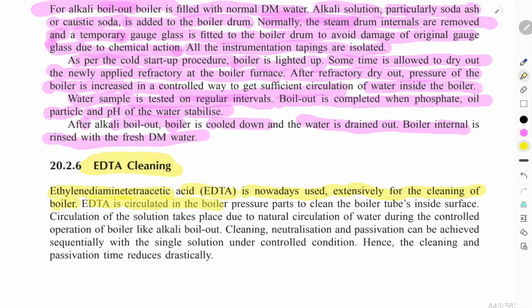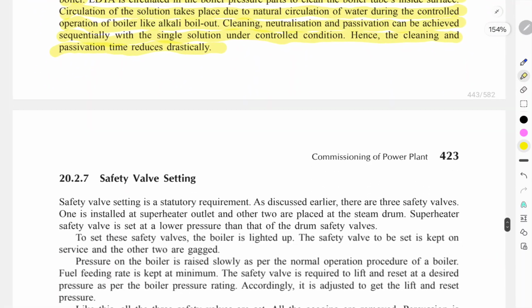EDTA is circulated in the boiler pressure parts, to clean the boiler tube's inside surface. Circulation of the solution takes place due to natural circulation of water during controlled operation of the boiler. Alkali boil out, cleaning, neutralization and passivation can be achieved sequentially with the single solution under controlled conditions, hence the cleaning and passivation time is reduced drastically.